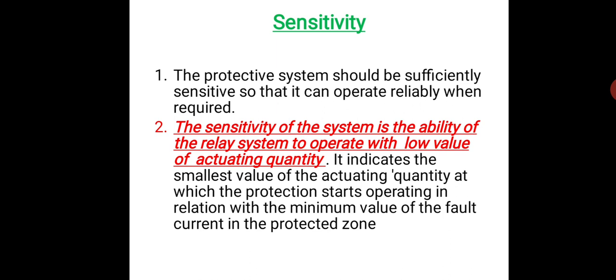Okay. Again, based on different faults, current will increase. In some cases voltage will increase. So when a fault occurs, current will increase. This increase in current will actuate your relay, so what current will actuate your relay is the low value of actuating quantity. At what value of that actuating quantity the relay should operate, it will be decided. And for a very small value of that actuating quantity, if your relay is operating, it means your relay is said to be highly sensitive.